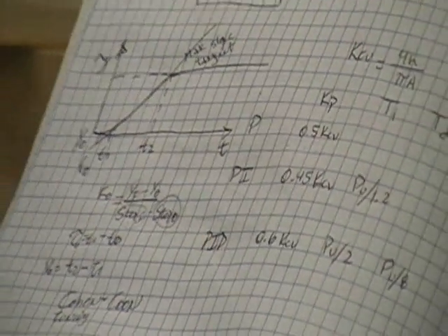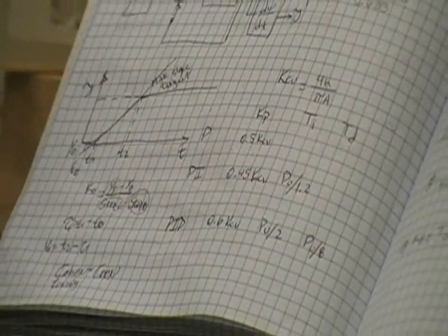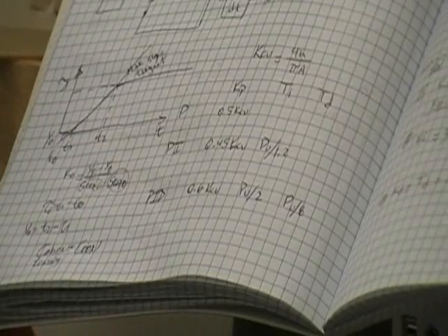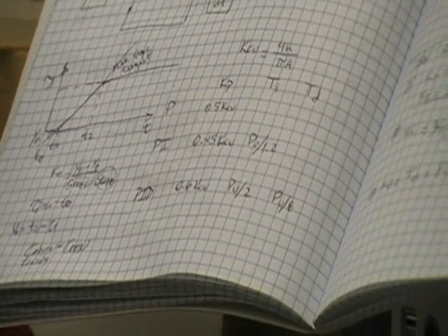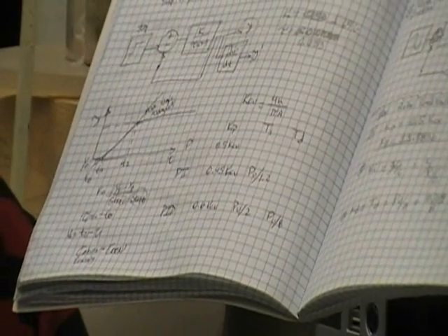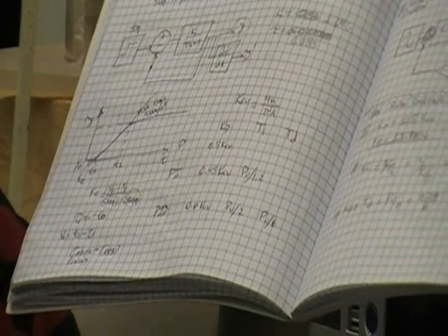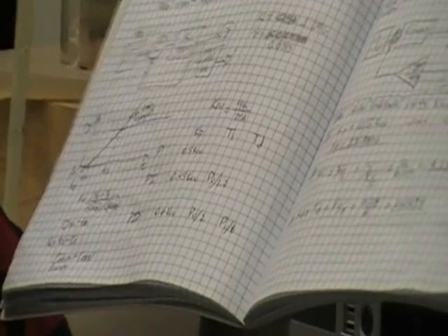Once you have this, again, go to the slides that you downloaded from the Mechatronics class, look up Cohen-Coon tuning, go to the table, plug in these numbers in the formulas over there, and get the gains. Note that in the Cohen-Coon tuning, they use Kp, Tr, and Td. It's the same as ZN, except Ti is now called Tr, and so here Ki would be 1 over Tr, and Kd would be Td, and Kp would obviously be the same.